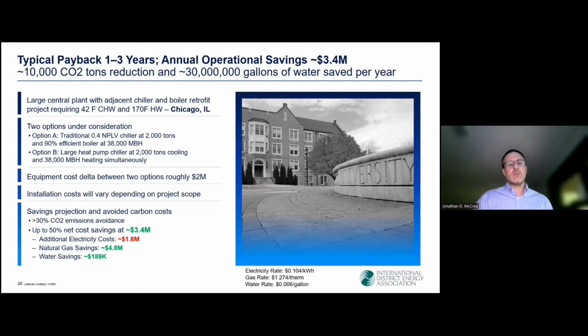So as far as the savings projections go in this case, we have a natural gas savings of a whopping $4.8 million per year in that cost. We have an increase in electricity costs of 1.6 million because the heat pump is certainly going to draw more power. And then we have a water savings that's 30 million gallons per year because we're not sending anywhere near as many tons out to the cooling towers. So we have a lot less evaporation with that. And that adds up to 189,000 in additional cost savings. So the net cost reduction, once you consider all of that, comes to $3.4 million per year.